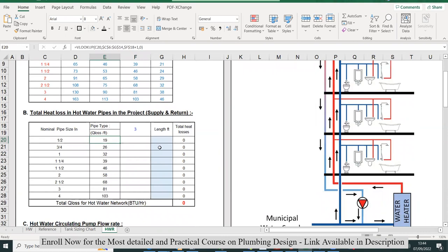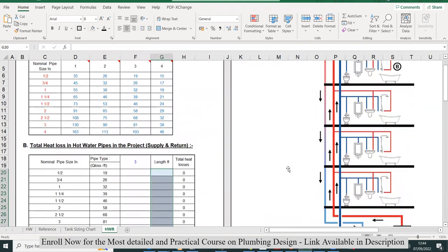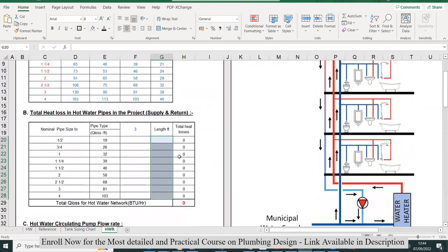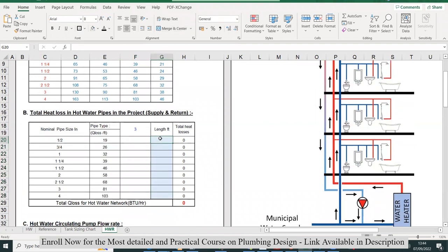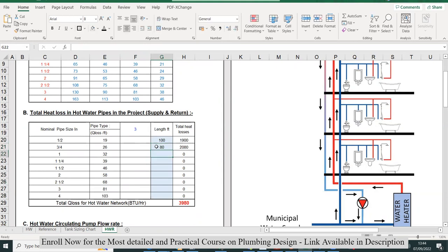Now I have the heat loss values for one foot. I have to calculate the total pipe length of half inch, three-quarter, one inch, and one and a quarter for this complete project. I'm assuming, for example, for half-inch pipe, the pipe length is 100 feet—50 supply, 50 return. For three-quarter, let's say it's 80 feet. I'm assuming just to save time, but for the actual project you have to manually calculate the total pipe length.